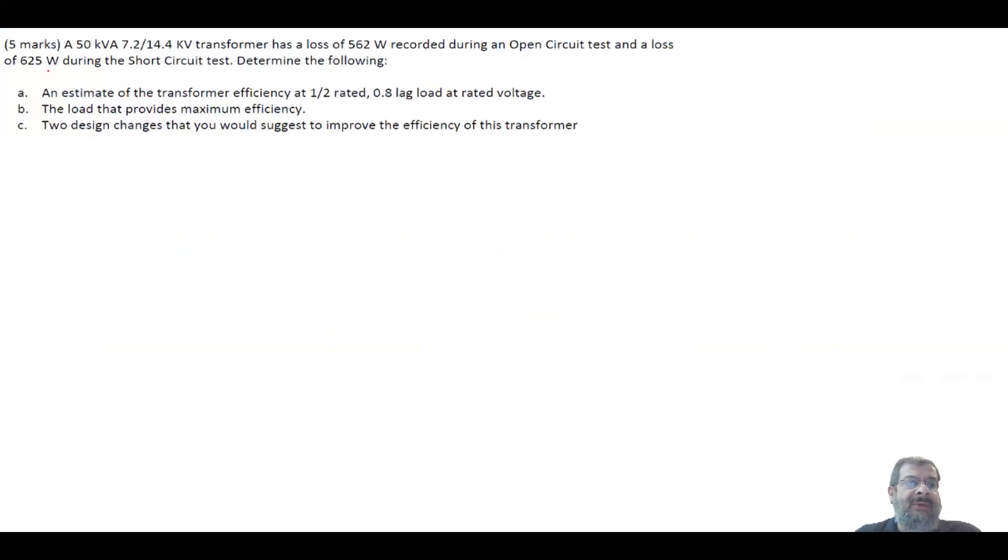It says here a 50 kVA 7.2/14.4 kV transformer has a loss of 562 Watt from the open circuit test, and a loss of 625 Watt during the short circuit test. First, find or estimate the transformer efficiency at 50% of the load and 0.8 power factor lagging at the rated voltage.